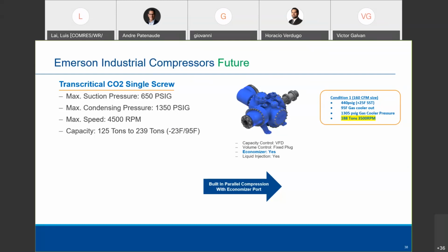It's really leveraging a product that was developed for the gas compression space, where you need a high pressure, high capacity compressor to do the job. So we have an existing shell that can handle some high pressures. So the team looked at saying, well, we've got this compressor that's already designed and being sold into the gas compression space. And it has an economizer port like these screws do, which we'll talk about in a few minutes. It's got a lot of unique features. Their bearing system, on ammonia, is warranted for 15 years because there's no external thrust. The bearings are completely balanced, which is a really cool feature to have when you're dealing with high pressure systems. So leveraging that technology for CO2 makes a lot of sense.